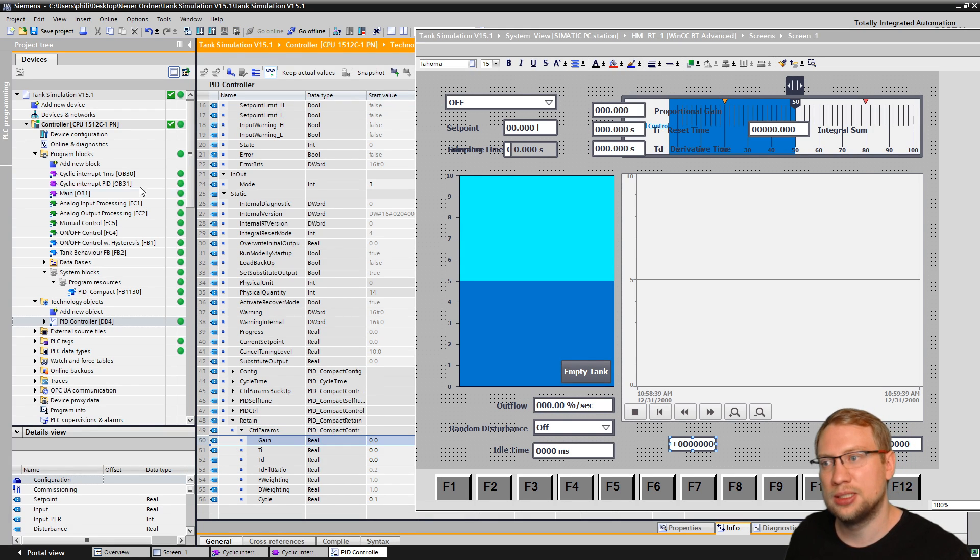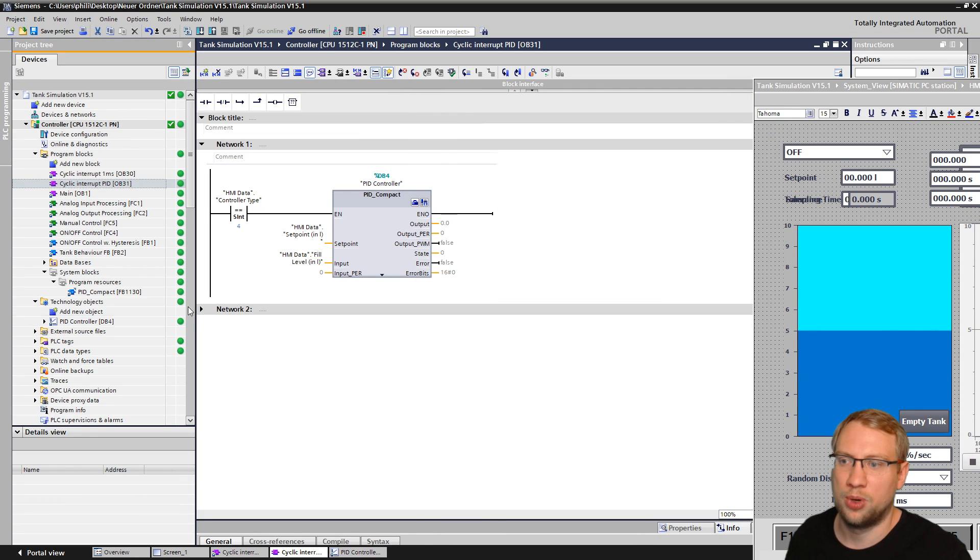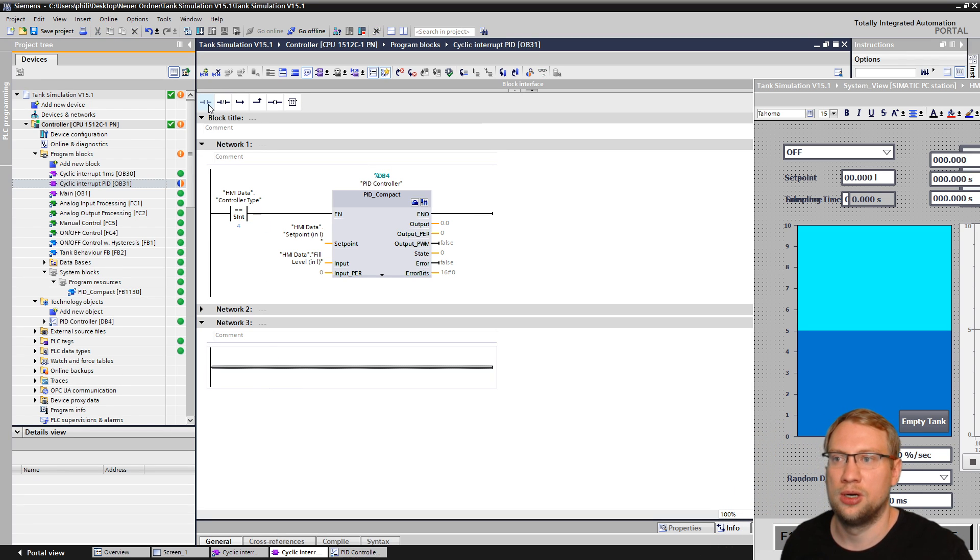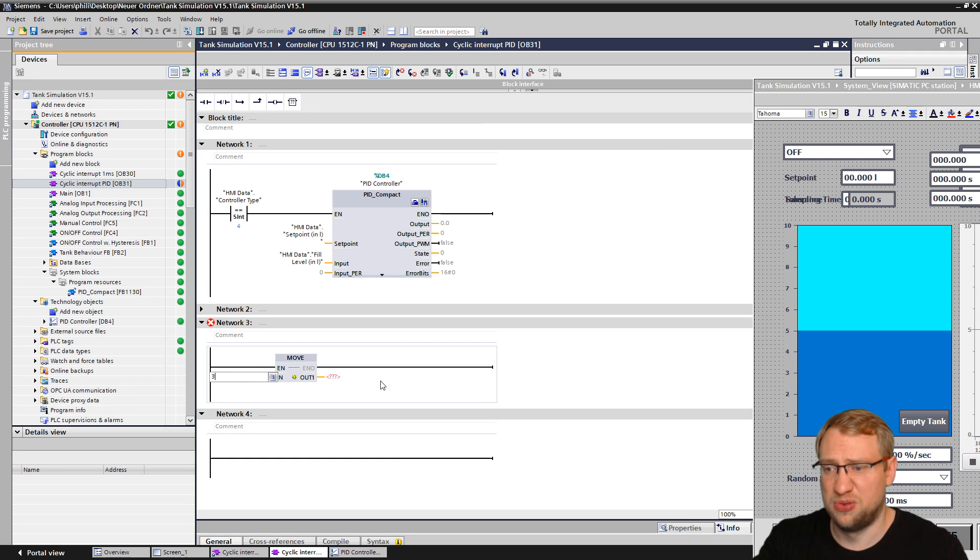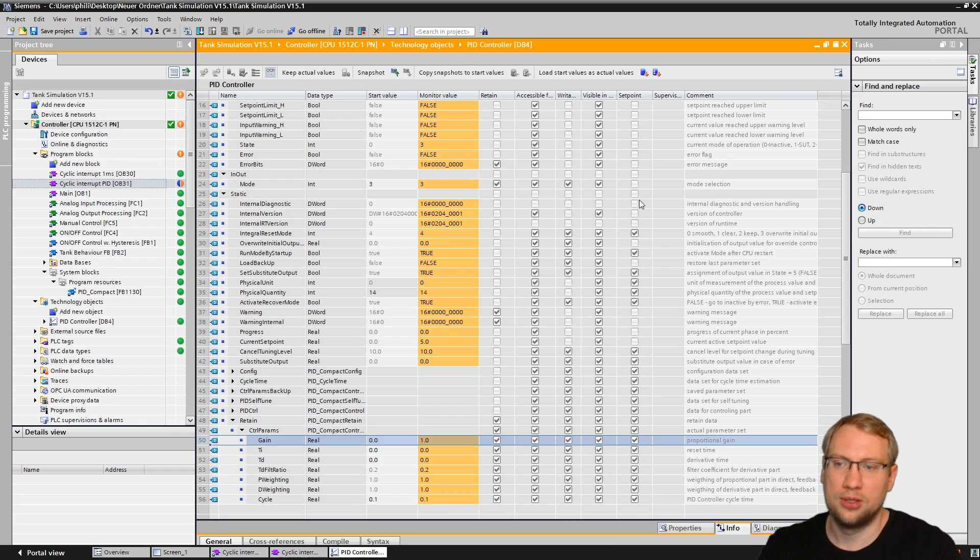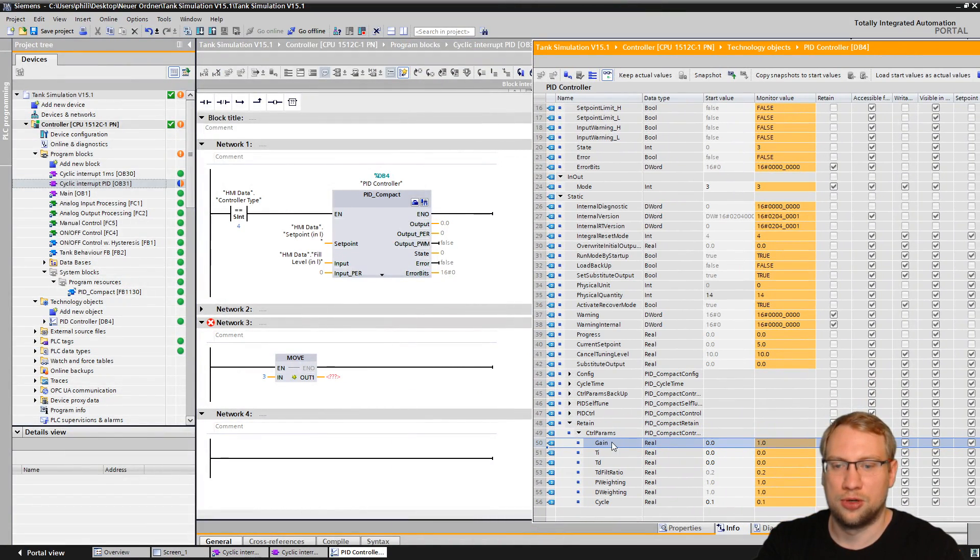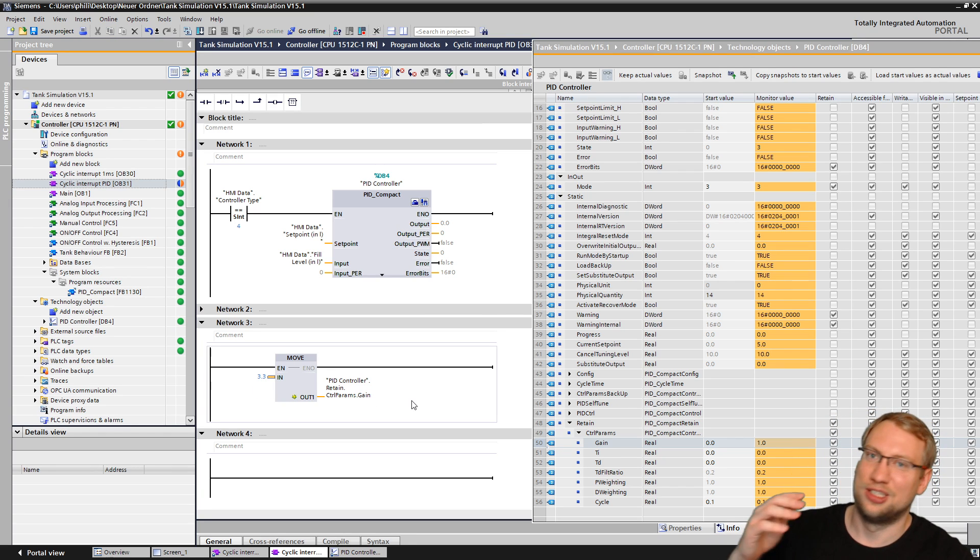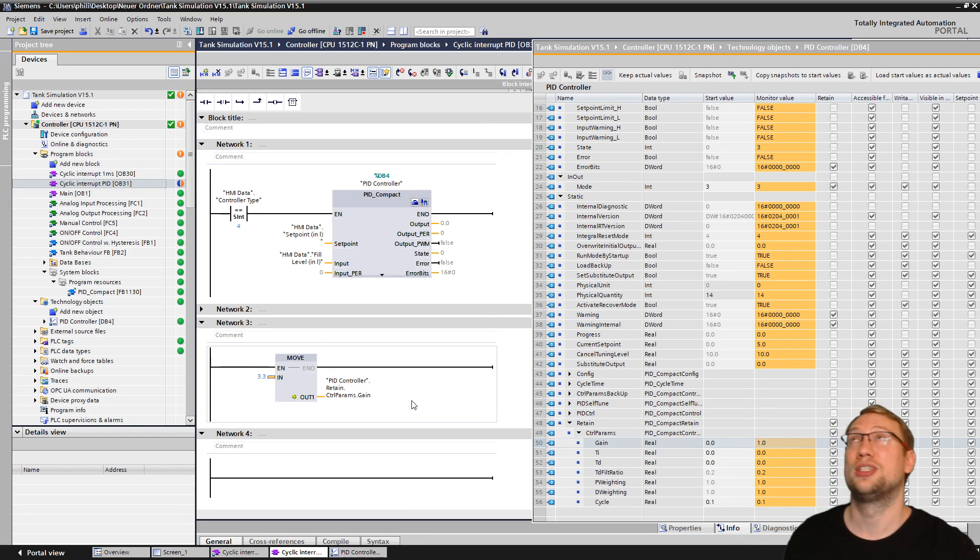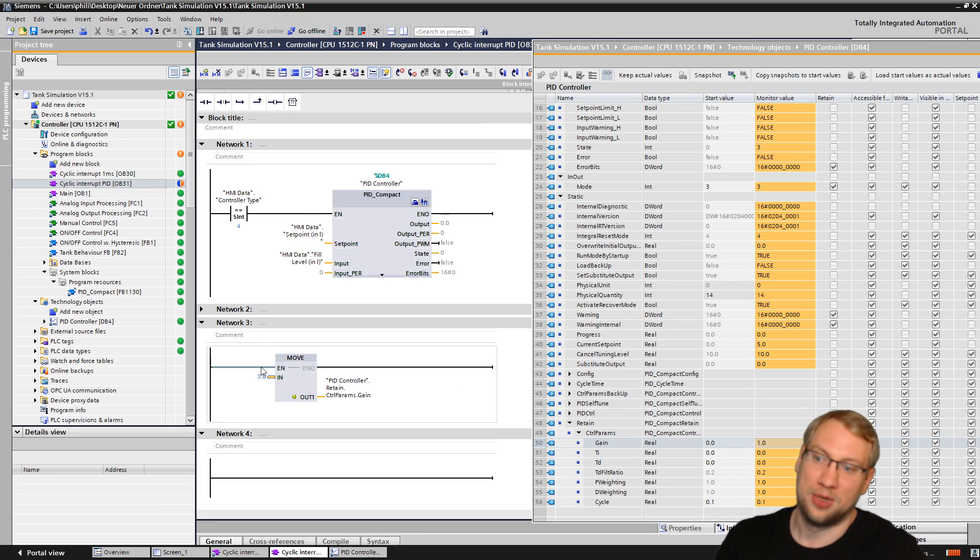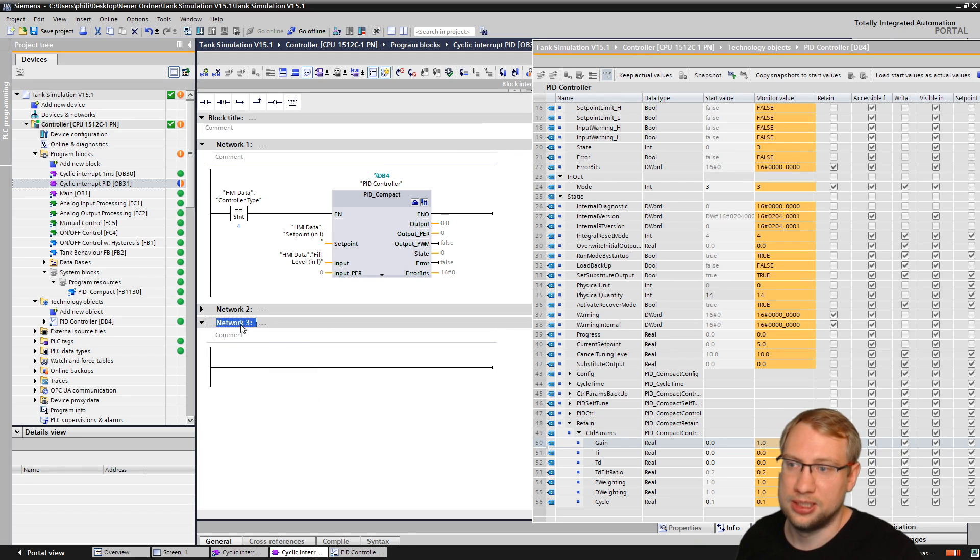The same is if you want to change it during your program somewhere, right? Let's assume I have one network that evaluates, you want a strong controller, you want a weak controller. So I'll add a new network here. And I can basically, if I want, let's use a move block, whatever, it doesn't matter. Move a three into the data block. And now I go back to my PID controller, the data block view. And I can just drag and drop that on here and I can change it in runtime. Of course that is now a wrong data type, 3.3. It's a float, so it needs to be separated with a dot. If it's just a three, that's an integer, it won't work. I could write 3.0, there we go, that works. But not three, three doesn't work. Now it automatically transforms. So you can also change those in your program. Very simple, very easy.